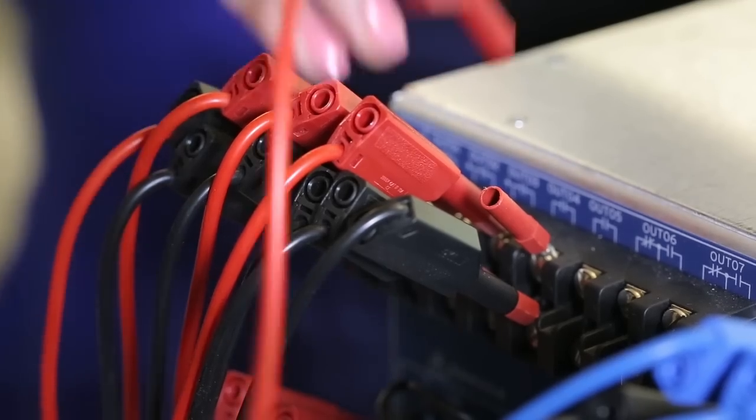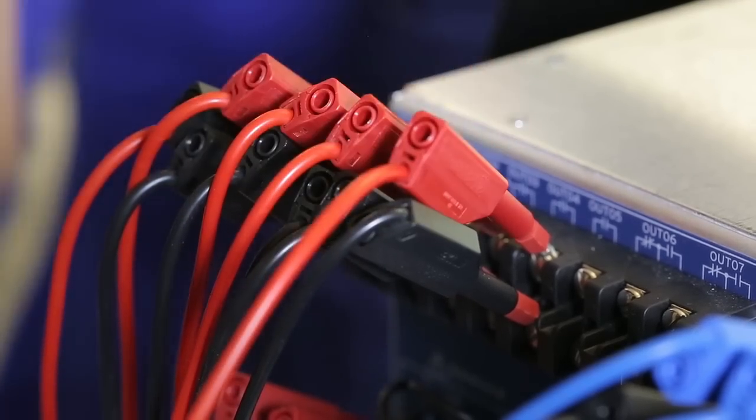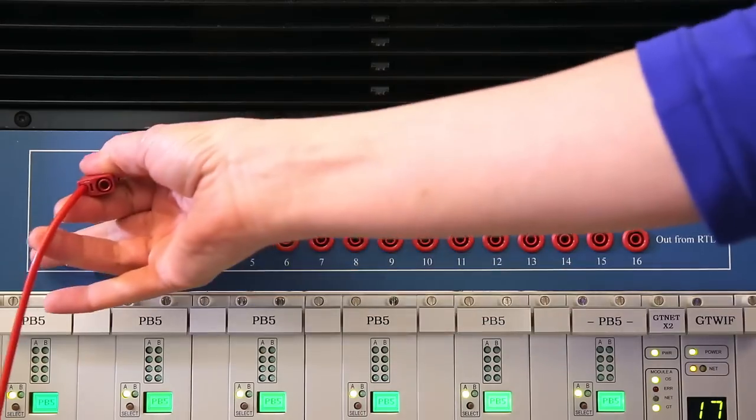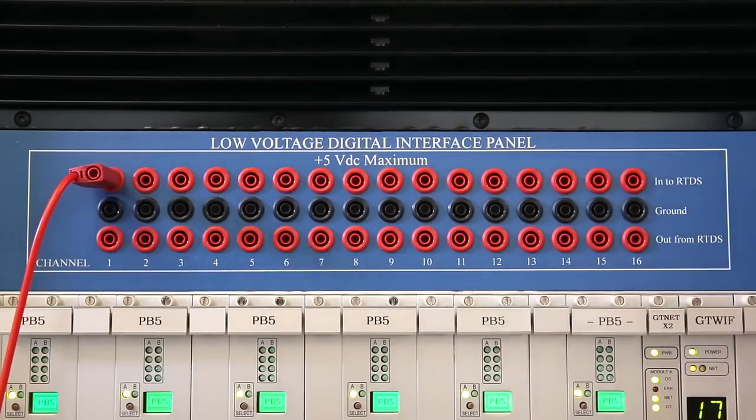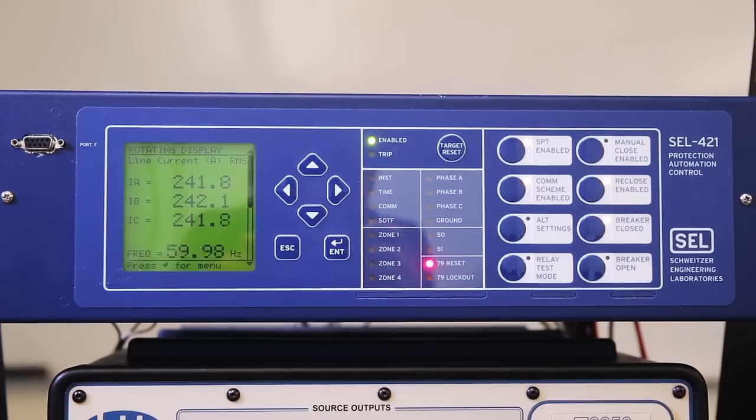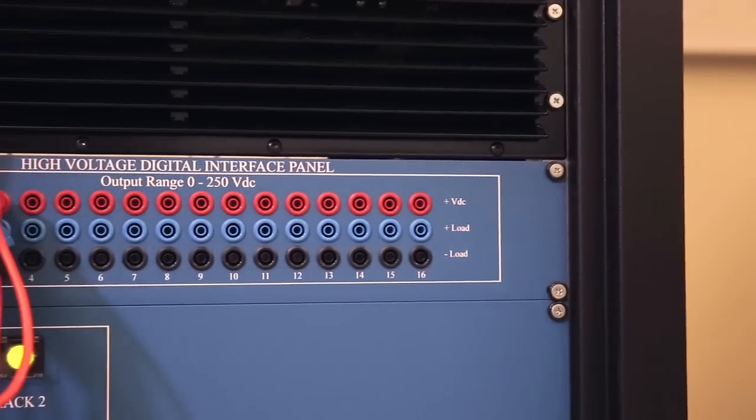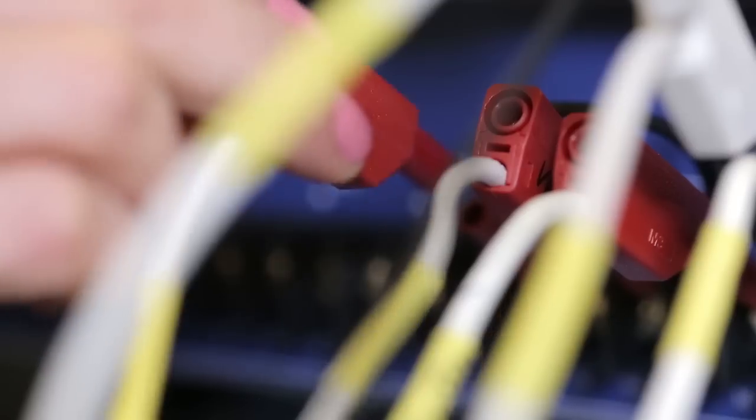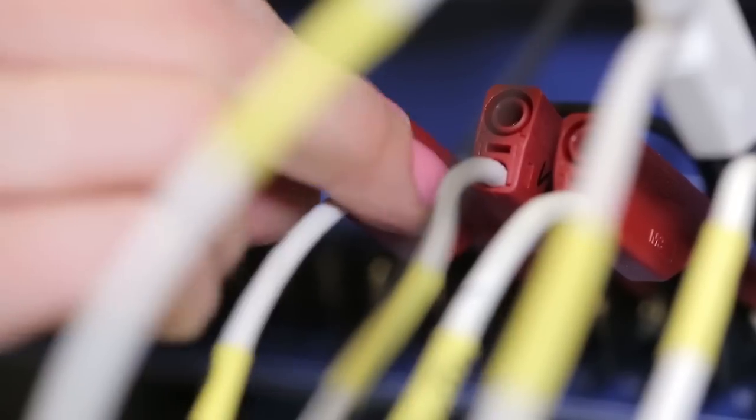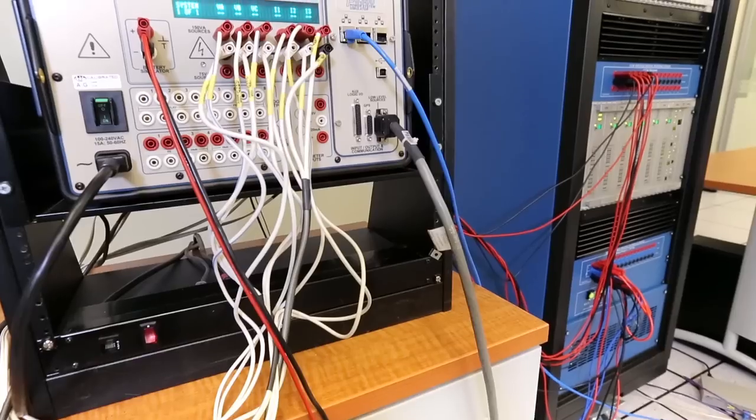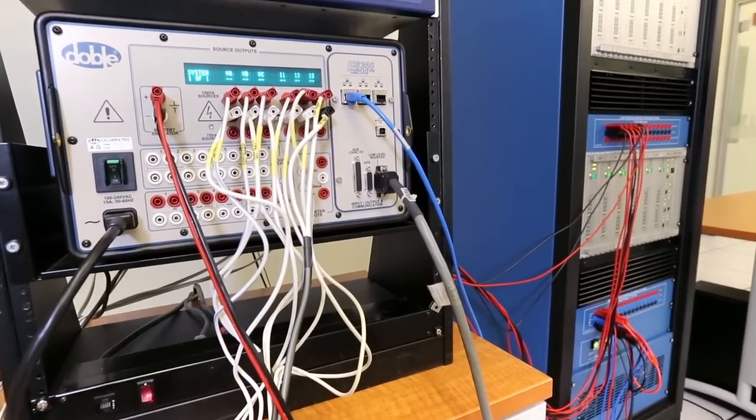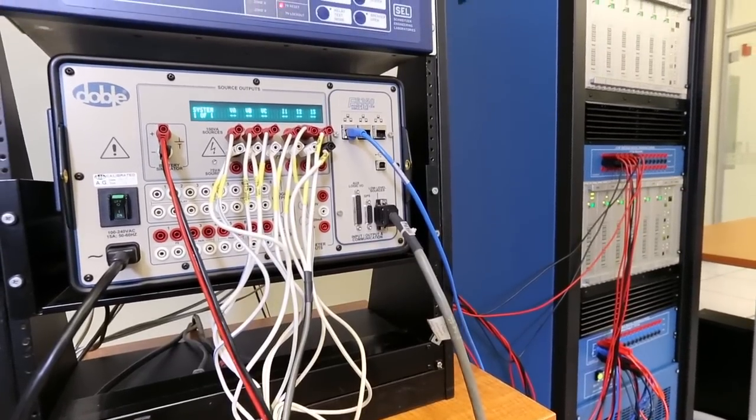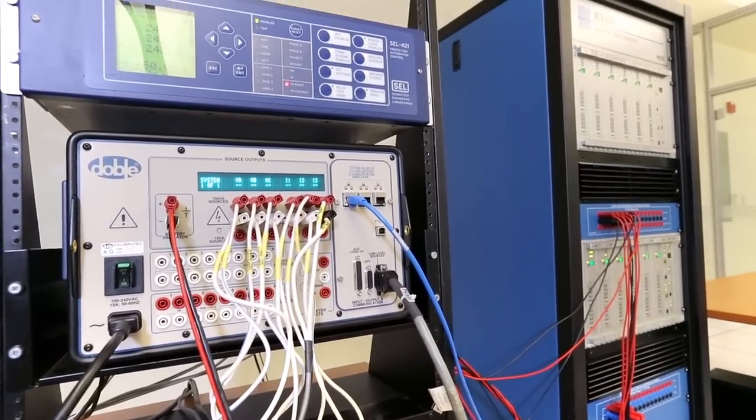The protective relay's output contacts are connected to the RTDS simulator's digital interface panel to communicate breaker commands. The simulator's high voltage panel is connected to the relay's input channels to communicate breaker status. In this way, we've created a closed loop between the RTDS simulator and the protective relay.